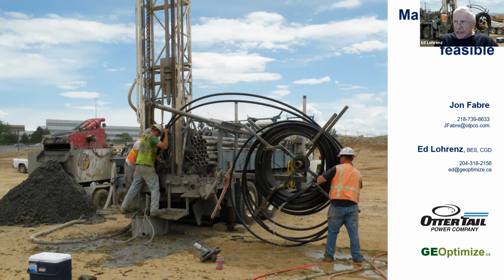we're able to look at heat pumps that are capable of producing 140, 145 degree water, using that to dump the heat into the ground. So we've got to basically increase or move the temperature range that the heat pumps were capable of. Most off-the-shelf heat pumps using R-410A, for example, you don't want to run them at much higher than about 100, 105 degrees Fahrenheit, that is about the top end. They start getting pretty inefficient. But with 134 refrigerant, some of the heat pumps are capable of running at 140, 150 degrees reasonably efficiently. So using that, just raising the temperature range that we're working with, and taking advantage of the aquifer underneath it, that would have made the project feasible.